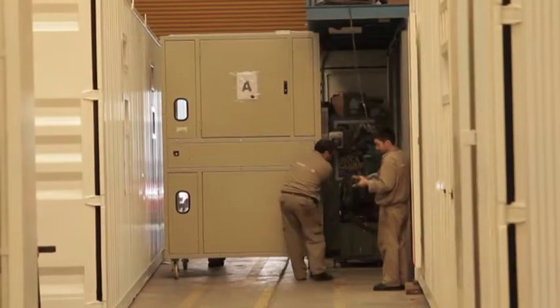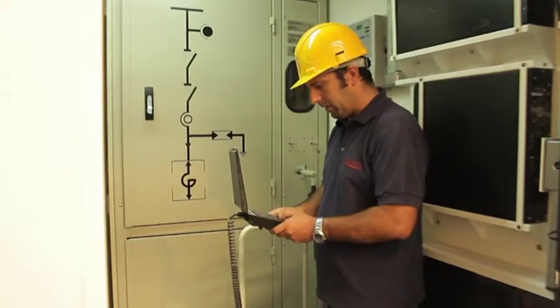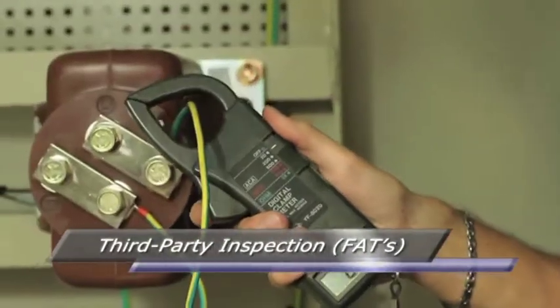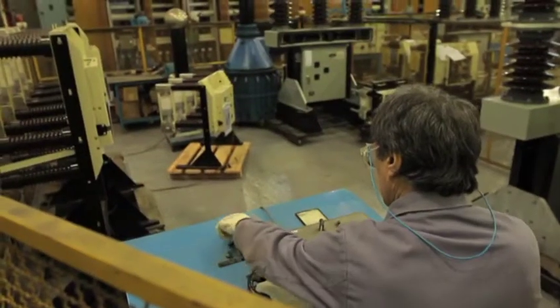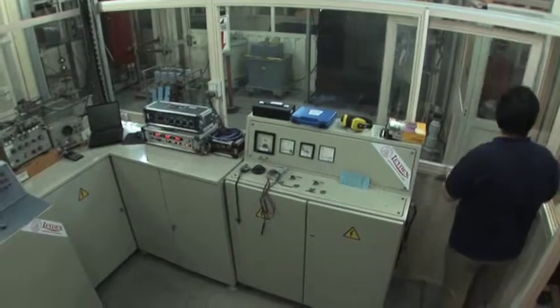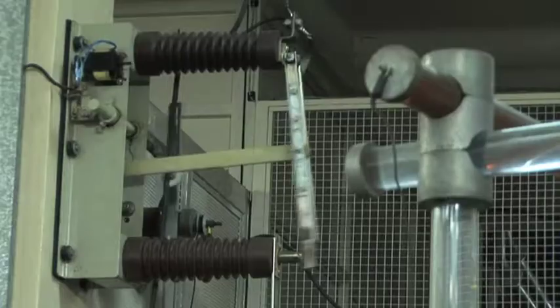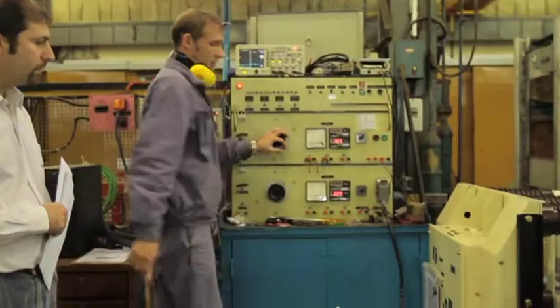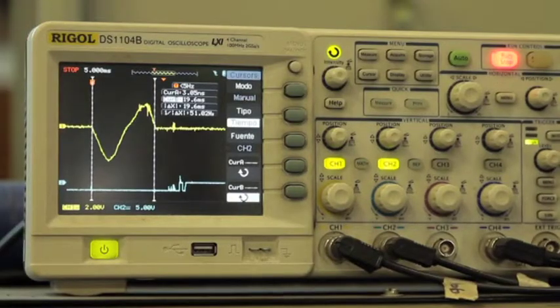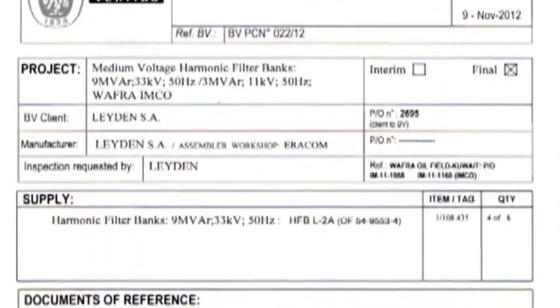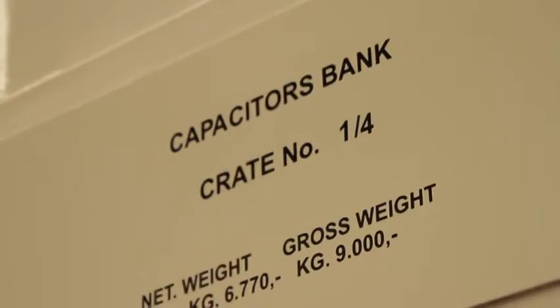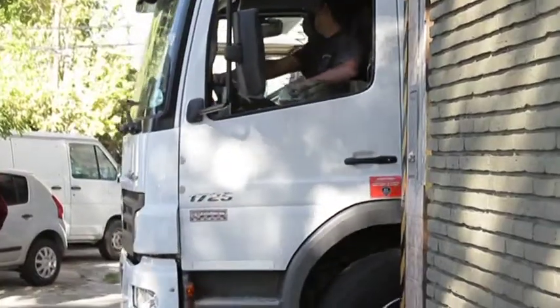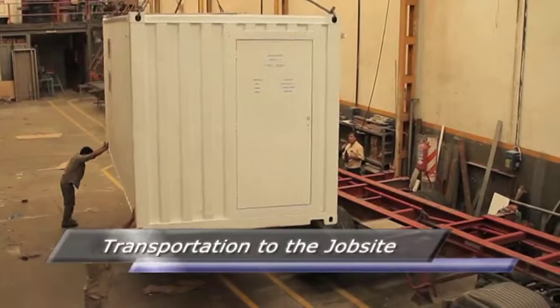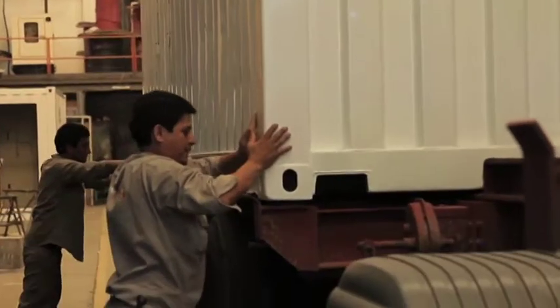Harmonic filter banks were completely factory pre-assembled and tested under the supervision of a third-party inspector, Bureau Veritas International, before being released for shipment to the job site. Besides, all key components, such as capacitors, filter reactors, circuit breakers, disconnector switches, instrument transformers, and so on, were individually tested by independent inspectors. Some of the components were also type tested before approving their use in the filters. The adoption of standard containers as enclosures for harmonic filter banks simplified ocean transportation, since they occupy exactly the same space and can be loaded and unloaded in the same way as normal freight containers.